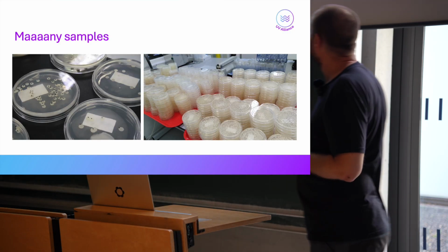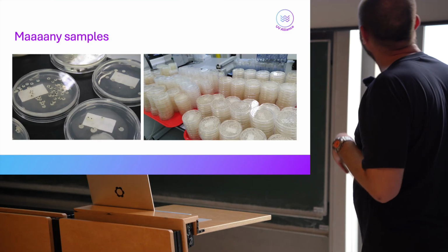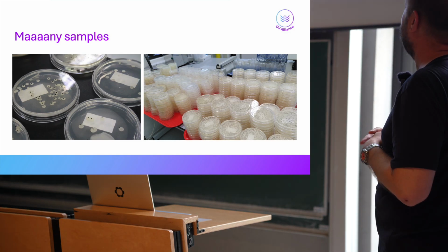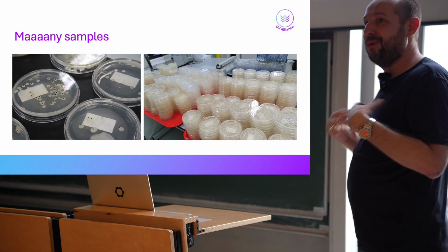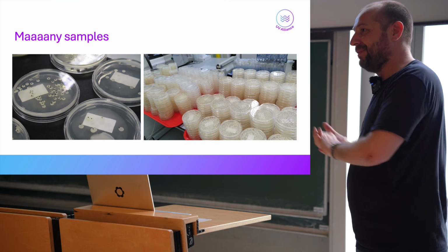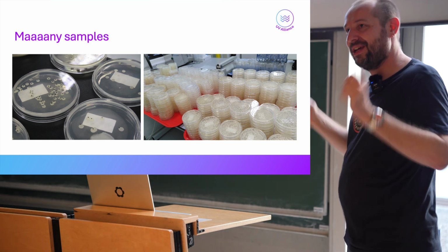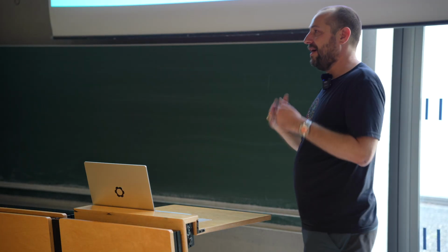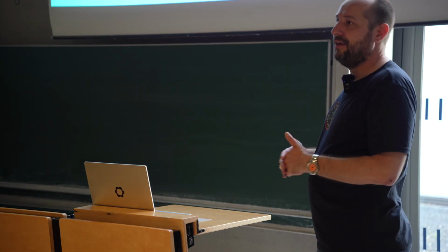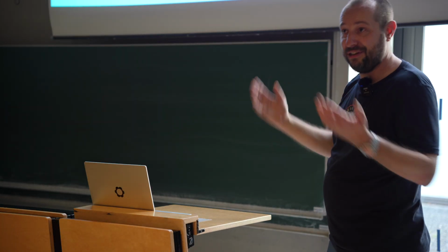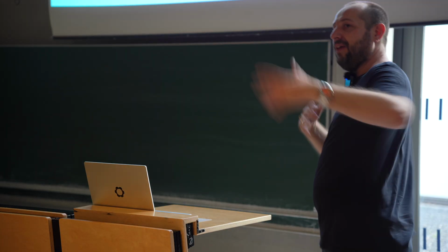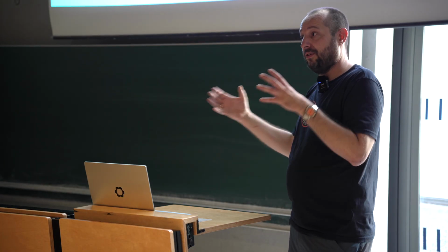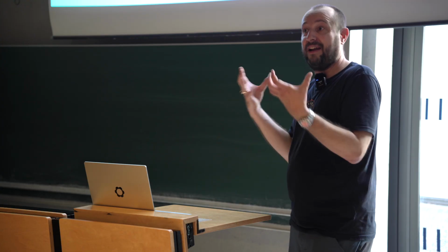This is an example of when we did 4 systems in our lab. And we had to plate out, I think, more than 800 plates. We don't do that. We have a deal with a lab in the neighborhood, so we just bring the bottles and they plate it out. But you have to count every colony, you have to count every dilution, you have to count every transmittance, every dose. And all these values together, if they are within certain statistical constraints, produce a validated system.